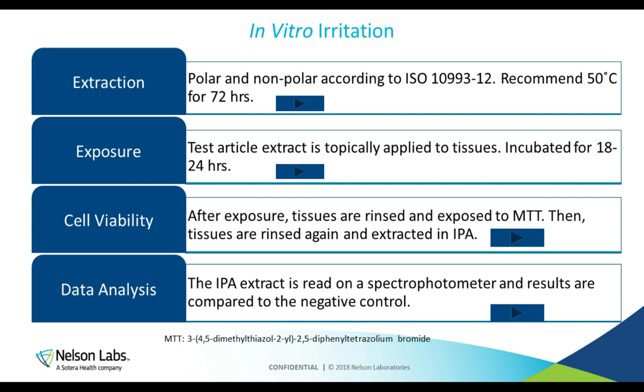So what we recommend is if you're within plus or minus 5%, so 45 to 55%, that additional testing would be a good idea, and possibly, depending on the risk of the device, we might recommend that you move forward with some in vivo testing to confirm the result. So, as much as we want to replace in vivo irritation testing, we may still have to go there. So this is just looking at a huge reduction for irritation testing at this point.